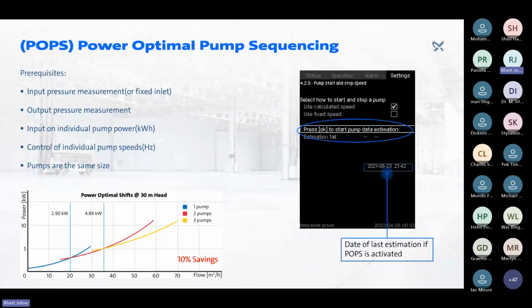Another new method of control for pumps would be something called power optimal pump sequencing. With a multi-pump system utilizing controllers, they include a sequencing algorithm purely based on pump speed. The number of pumps running is based on the speed of the pumps, and in a set running with multiple pumps, we generally bring on the additional pumps when the pump speed is 85%. So let's say our flow increases, as you can see on the graph in the bottom left. As it increases and we cross 20 meters cubed in the system, we then need to bring in another pump in order to reach the additional flow requirements.